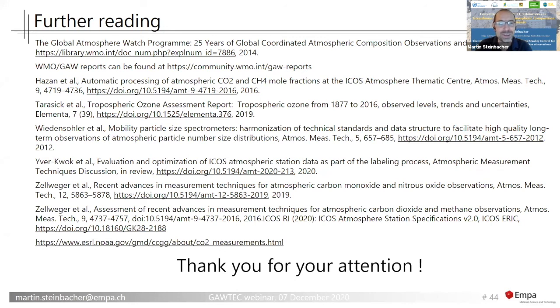I think that's the fast answer, at least. And the more calibration gas you have, the better. Usually the calibration gases should span the whole range of atmospheric concentrations you observe. Sometimes sensors are non-linear, then it becomes more tricky, but this can also be investigated when applying several calibration gases of known concentration.